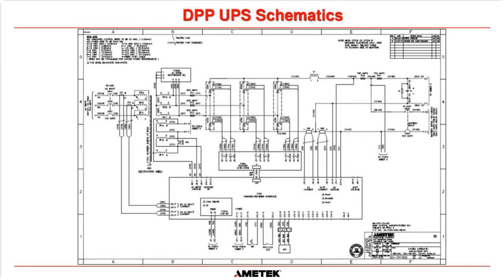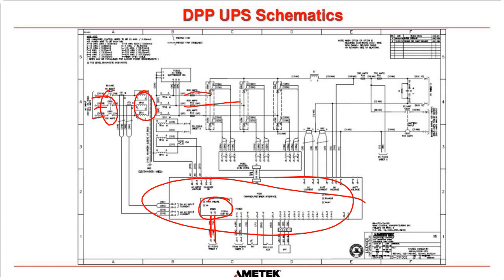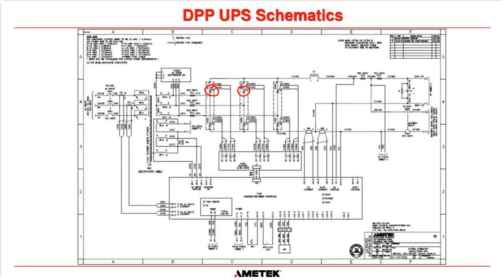Once again, here's our rectifier, and once again it goes in through a circuit breaker and then into a delta transformer. Okay, this is a digital board. So this is our communications board with fiber optics coming out here. So that's what connects to the brains of the system. And this is actually a digital charger, but the principle is exactly the same. We've got our AC going in here to our SCRs. So AC on this side, and then we've got DC coming out on this bus bar here. Okay, we're still using SCRs here.